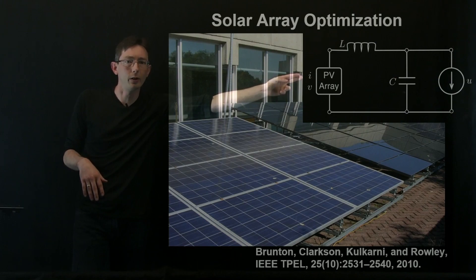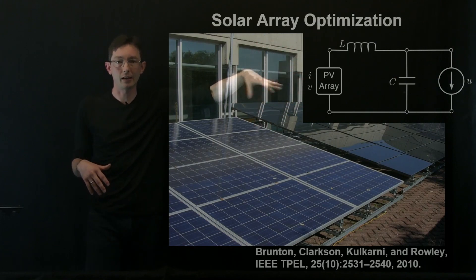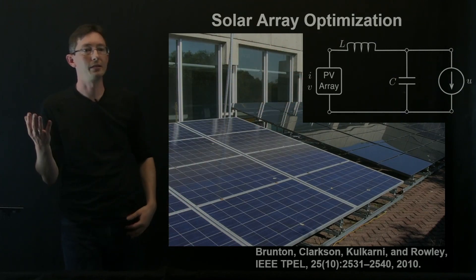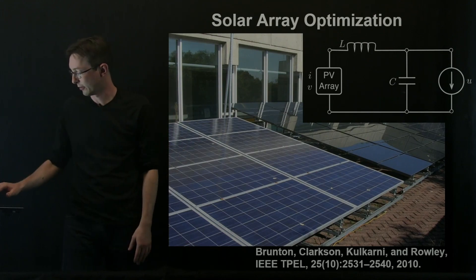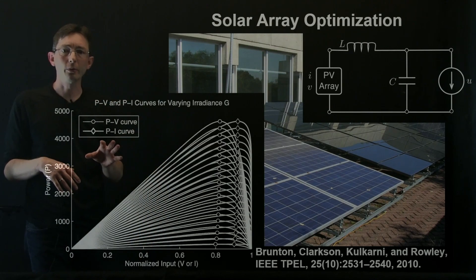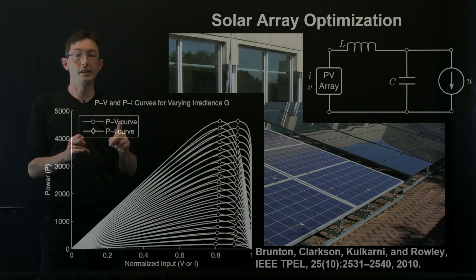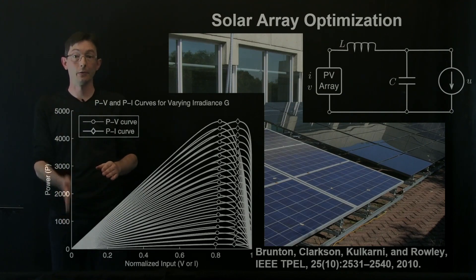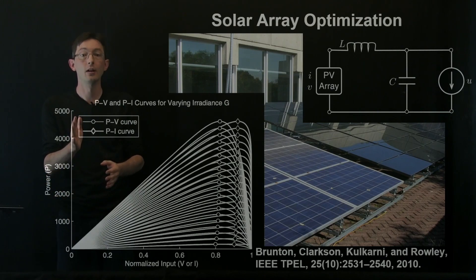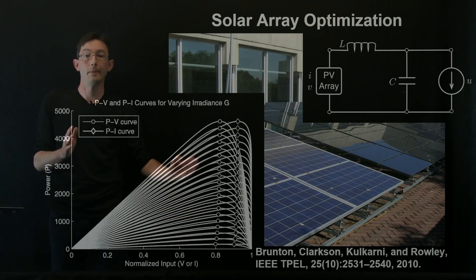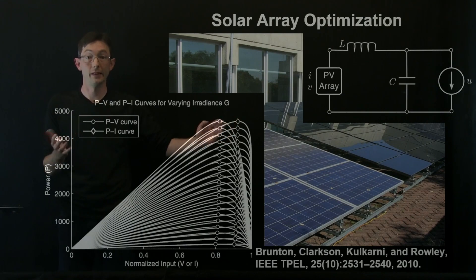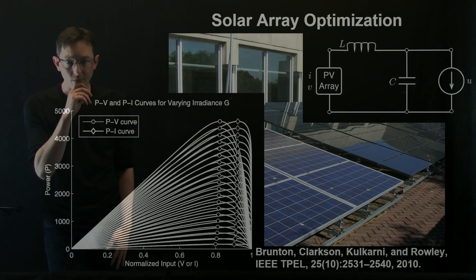So you can model your array using this basic diagram here. There's some capacitance, some inductance, and so on and so forth. And what you're really trying to do, so these are the power versus voltage and power versus current curves. You want to maximize the power. That's what you're feeding into the grid. You want to maximize the power by setting V or I to be at this peak, this optimizing value.